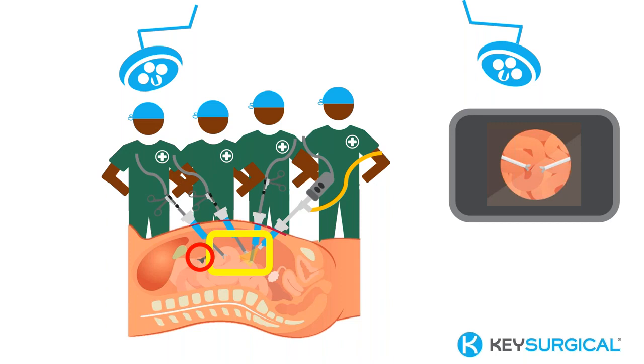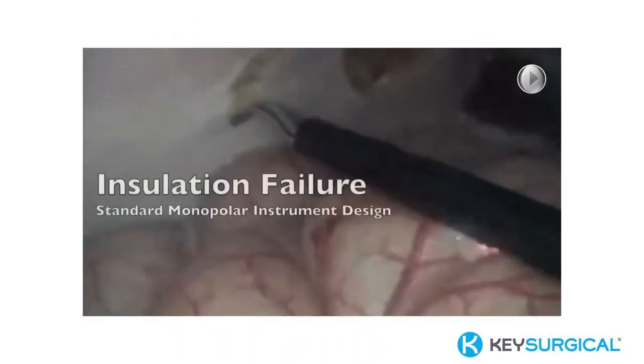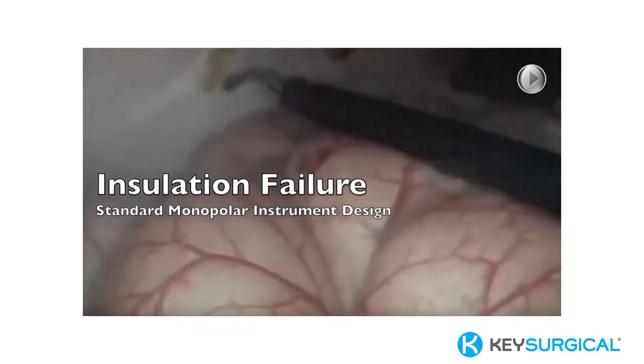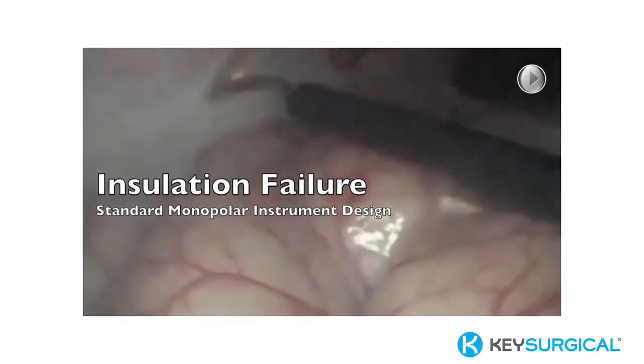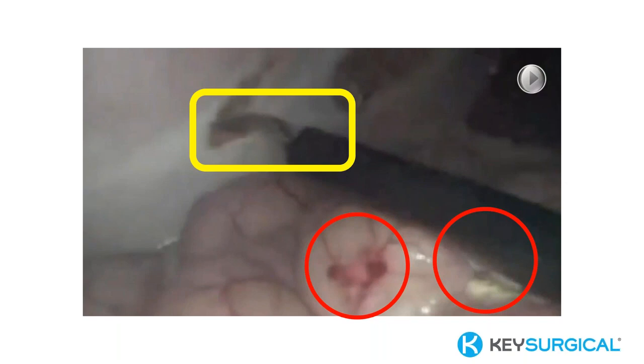So let's look at that video example that was made to depict the damage that insulation failure can cause. We'll let this play through for a second. You can see the tip of the instrument and where it's working. This is that yellow box on the patient that we just saw, which is what we can see. Now you see those red circles and our yellow box. The yellow box is what we're looking at and what we can see, and these red circles happen outside of that field of view, and that's where we get some of that damage.